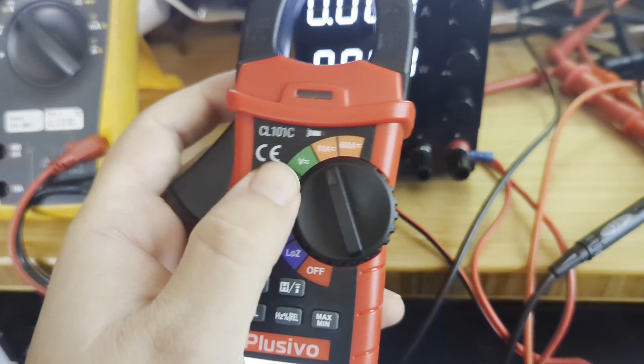As you can see here, I have it about negative 0.8. This is about as good as it gets. This is after calibrating. It was about 1 to 3, 1 to 2, kind of fluctuating. So as you can see, not very accurate on amperage if you're looking to get anything close to 10 or less. It was better when I got closer to the limits, let's say like 40 to 50 amps. It was much closer, but still off.